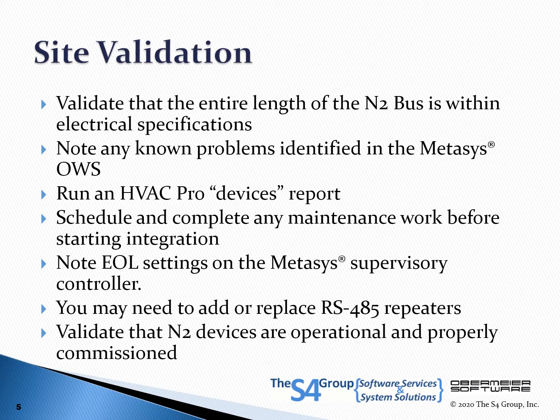RS485 repeaters need to be installed following the RS485 standard. This was not always done with Metasys installations because the NCM had custom circuitry. Repeaters age just like any other electronics and may be the source of intermittent problems. RS485 wiring standards must always be followed. T or Y connections will cause problems. These are especially likely in cases where an installation was modified along the way.